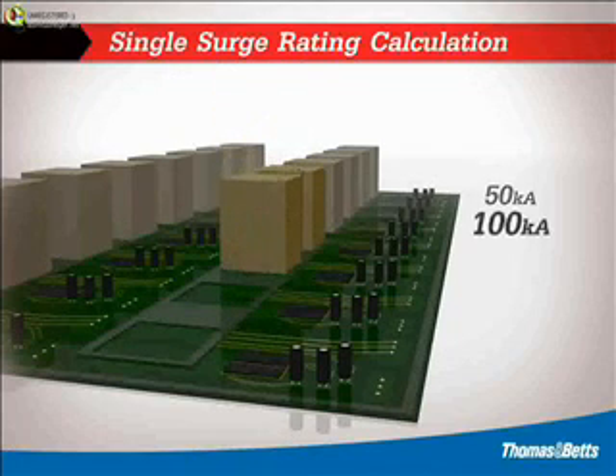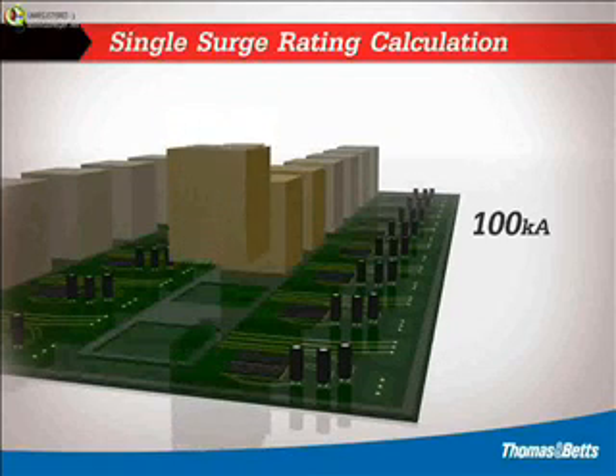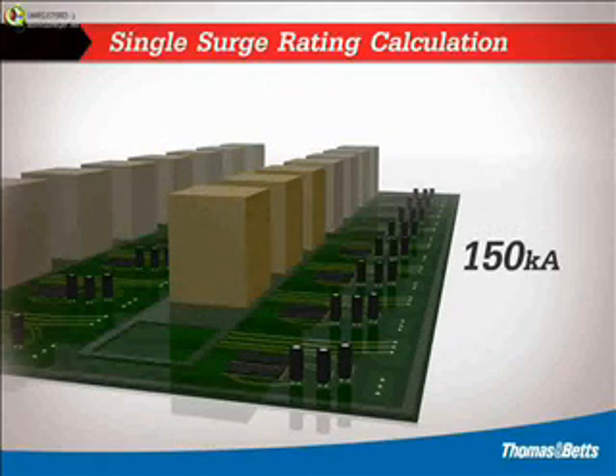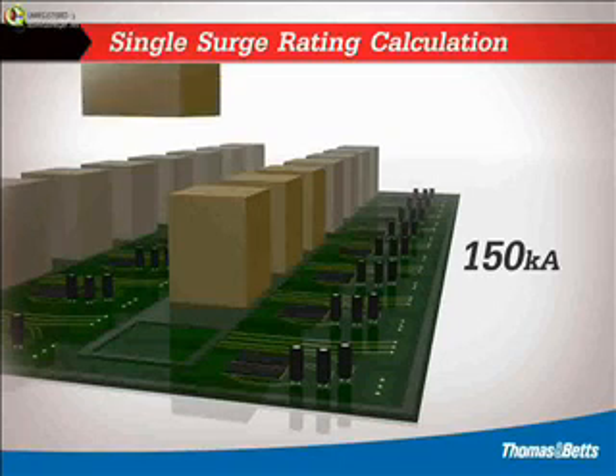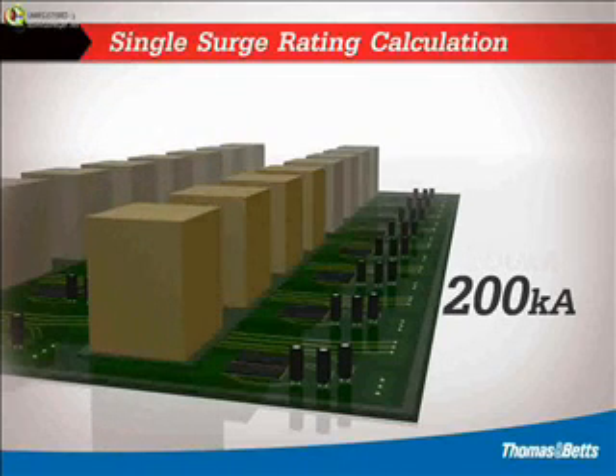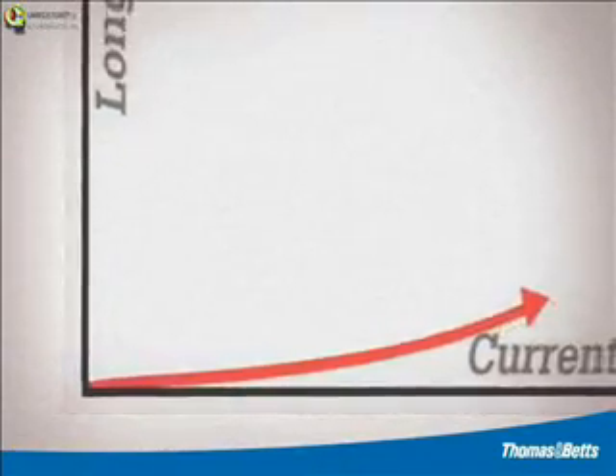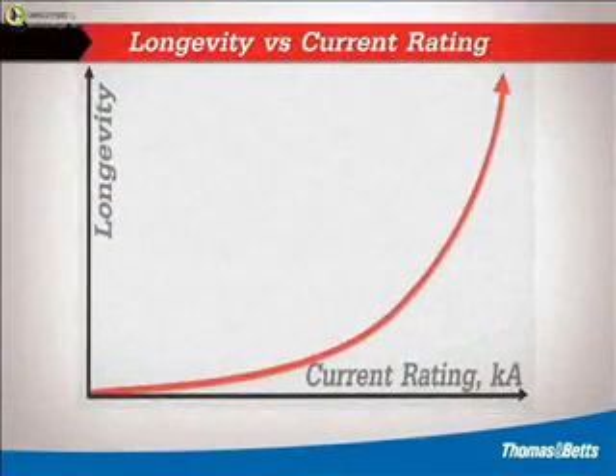The surge rating of the individual component can no longer be assumed once it is placed on a printed circuit board and becomes part of a system. Relying on calculated values does not guarantee performance. Higher surge ratings provide more protection and ensure a longer, useful life. Since the purchase price of the surge device increases with higher surge ratings, it should be important for the manufacturer to prove the product's robustness by providing a single surge test report.